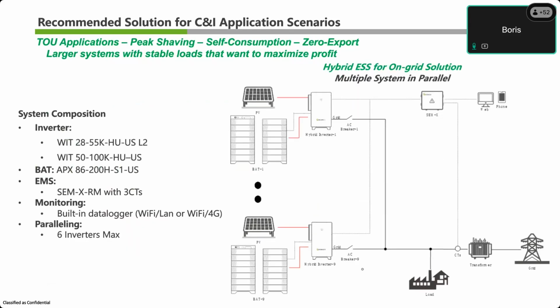This is the same application, but on a larger system. So we can parallel the WIT, but when we parallel the WIT, the only thing that changes is that we have to add an SEM-X-RM or some external EMS in order to manage and balance the systems. We sell the SEM-X-RM as an option for that, and it's our preferred option. It's just plug in. You don't have to do any programming. And the SEM-X-RM will do that for you, so it'll manage those inverters together, but one at a time independently, and make sure that they're staying balanced with each other.